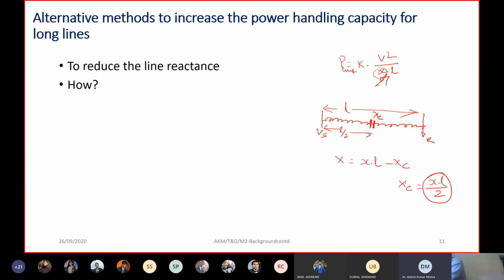Suppose the line could have a short circuit anywhere. Suppose there is a short circuit at this point, case one, a single line or three phase to ground fault, and case two at another point. The difference between case 1 and case 2 is that in case 1 the fault occurs just immediately before the capacitor, and in case 2 the fault occurs just immediately after the capacitor. In case 1, the fault current IF will be the voltage divided by XL by 2, since this is around the middle of the line.